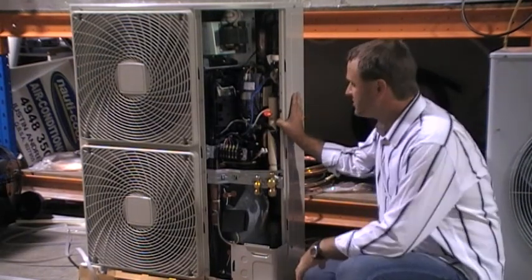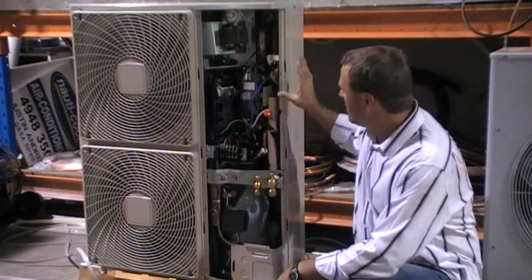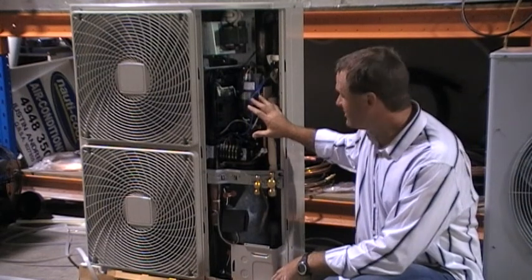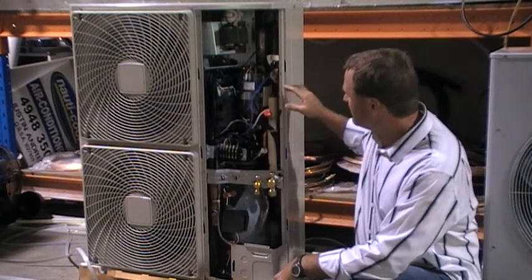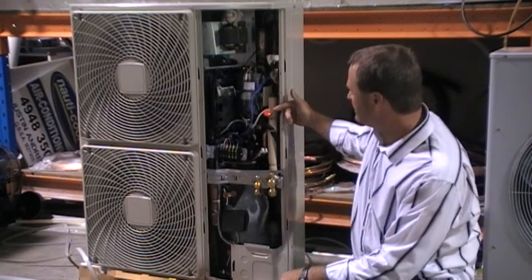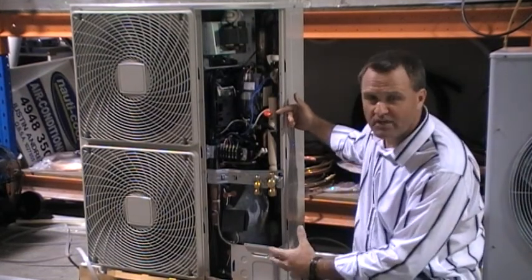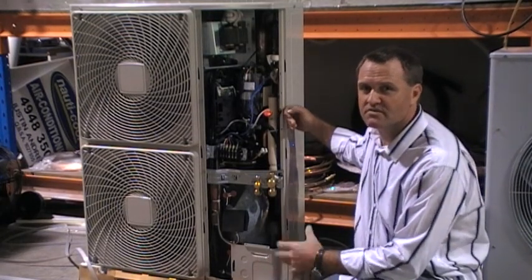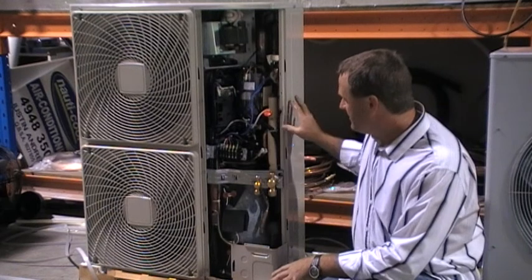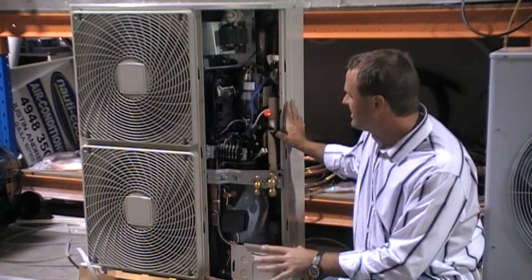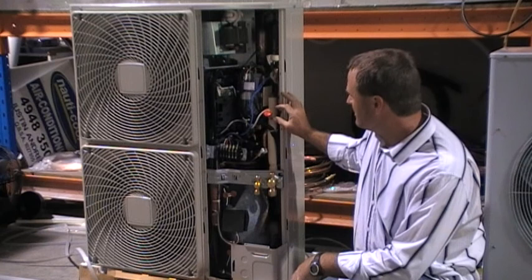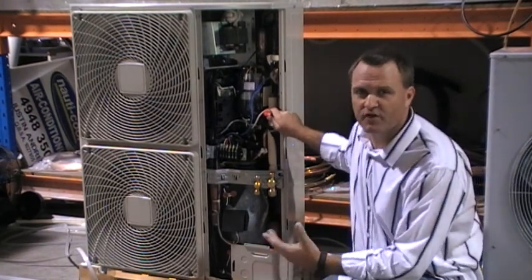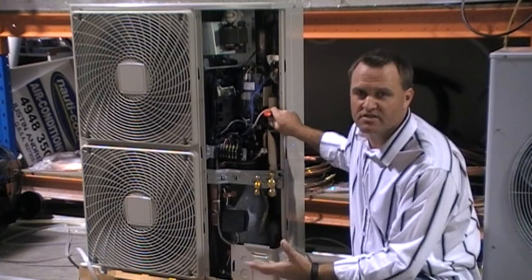Some of the disadvantages would be ease of fixing. They can be quite difficult to fix and diagnose. As you see, there is a number of PC boards in these, and they're really quite complicated to fix. Generally speaking, a lot of the time the technicians need to call tech support to get information to actually diagnose these properly. And inverters have had a long history with vermin strike, like frogs and geckos getting into them and shorting out the PC boards.